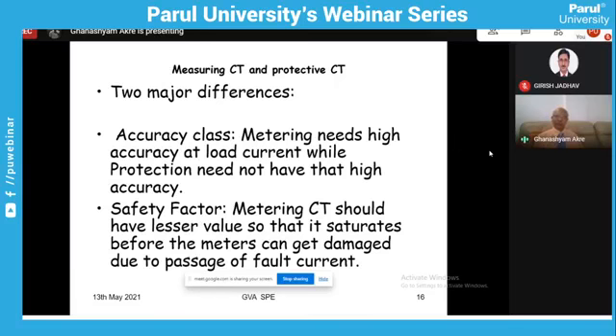See, protection is utilized for sensing if there is a fault. When there is a fault, current will flow in the system more than 2 times, 3 times, 4 times, or even 20 times. So there is no measurement at that stage. Only the relay will understand that it has drawn a much higher current than it is rated for, that it is subjected to a fault, so it should act. And that is why accuracy is not very important in the protection class.